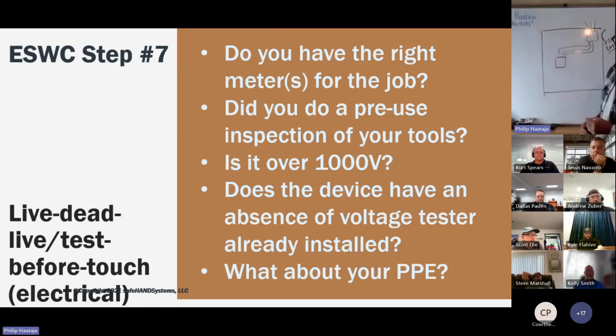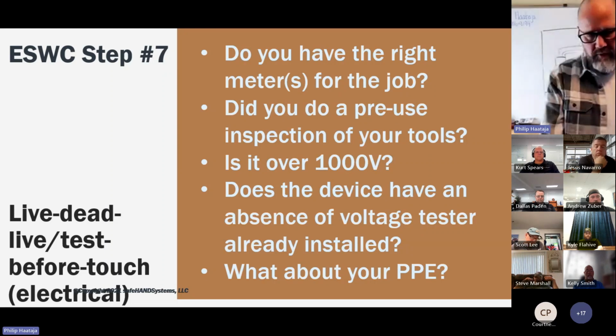Now, step number 7 says you have to do a live-dead-live test with your meter to verify the power is out.